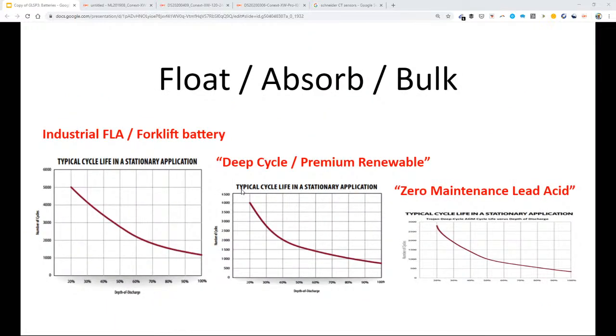When you look at the technical performance differences between sealed lead acid and unsealed lead acid, the unsealed lead acid batteries can be much more cost effective over the long run. The maintenance tasks on batteries are not very difficult, and the fact that it's unsealed lets water vapor escape, which needs to be refilled by watering your batteries. That also means you can subject the battery to more aggressive charges, sometimes a really high charge to condition it. So you can condition unsealed batteries, whereas you can't condition sealed batteries. That means sealed batteries cost more money up front, and they also have shorter performance and life overall.